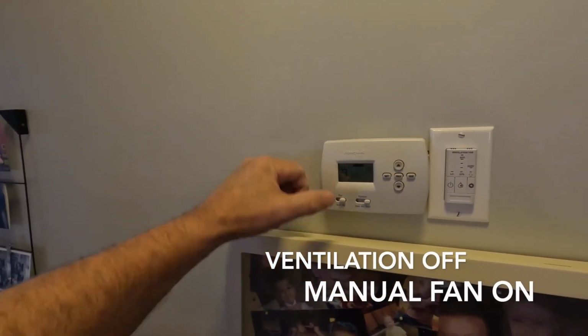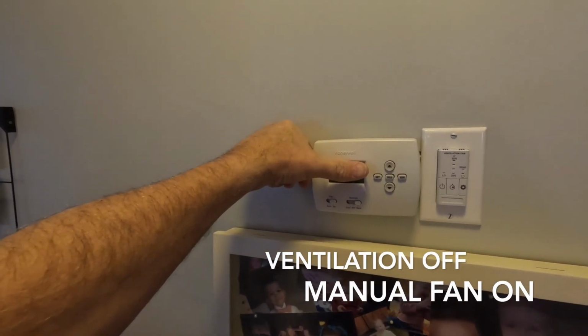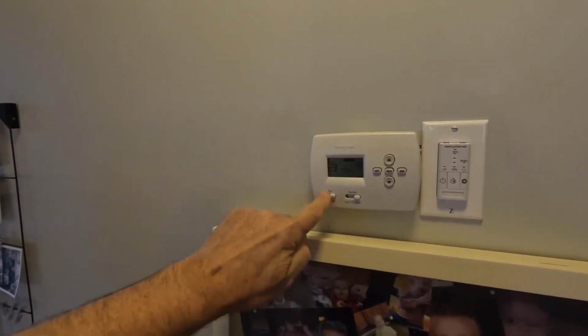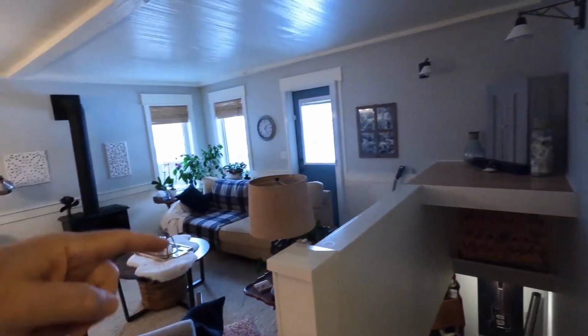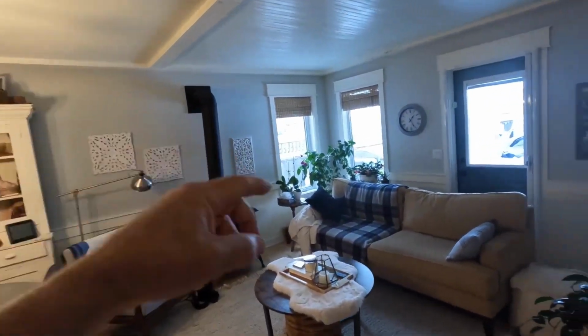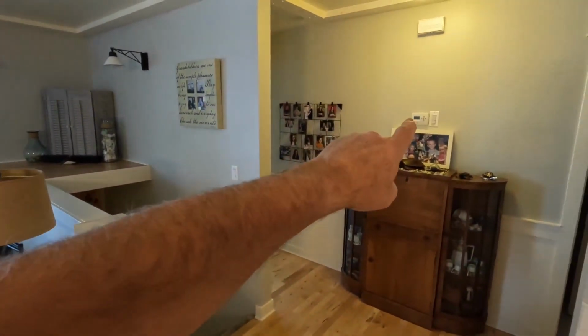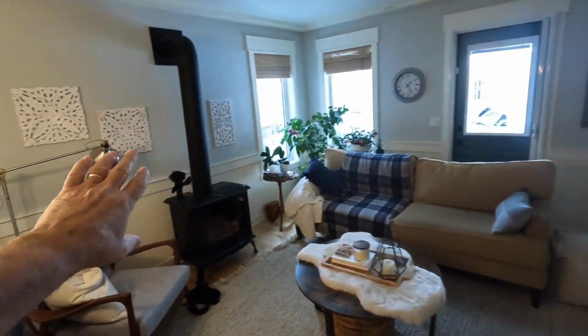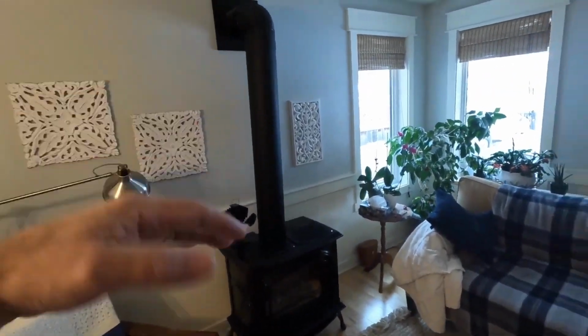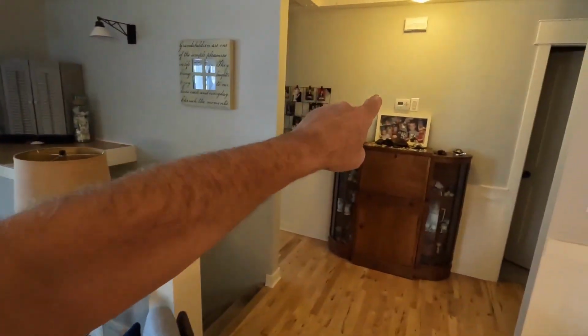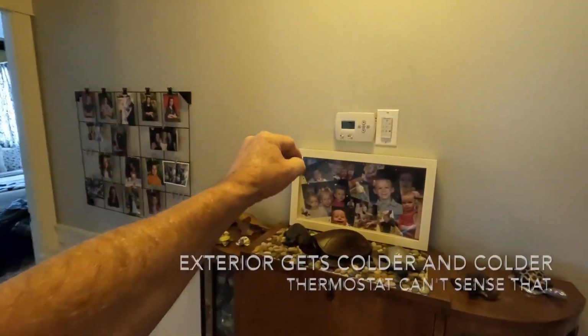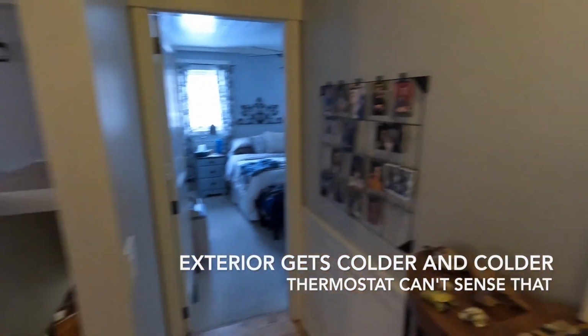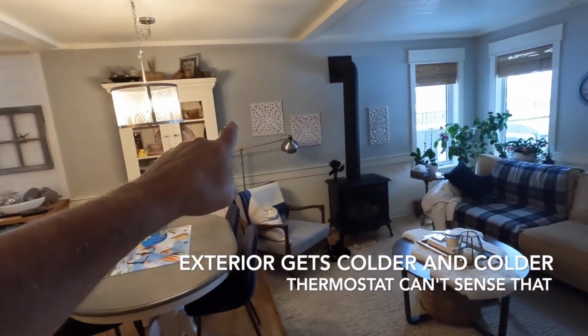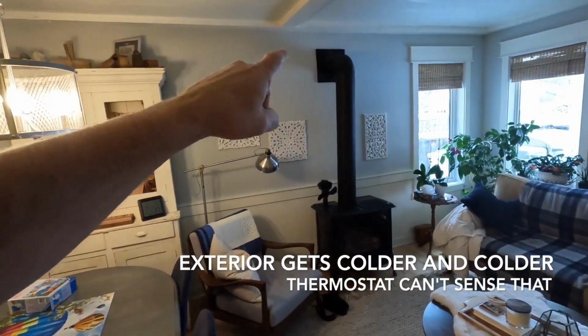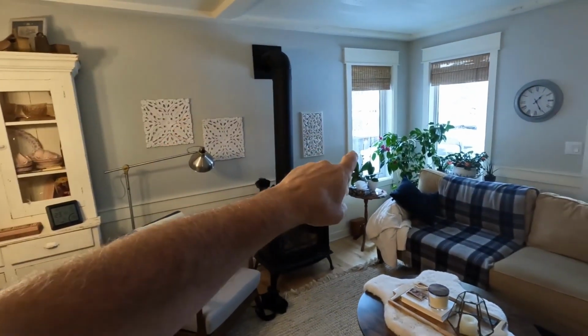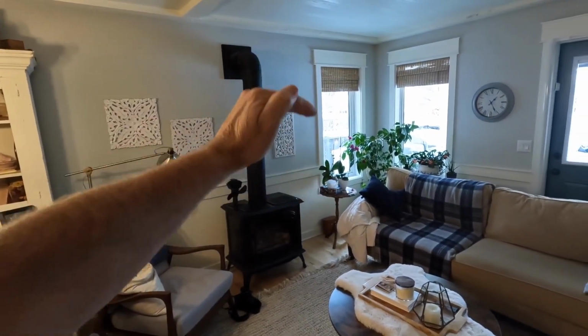So what I'd like to do is forget that number, set it to a comfortable temperature, and turn this to on. So now it's circulating the air throughout the house, moving it around, and that air, which is 23 degrees at the thermostat, is reaching the exterior surfaces to warm those up. Because what will happen is if I set that at 23 and I turn this to auto, before I know it, those surfaces over there are going to be 16, 15 degrees, and around the window, the stagnant air is going to be even colder.